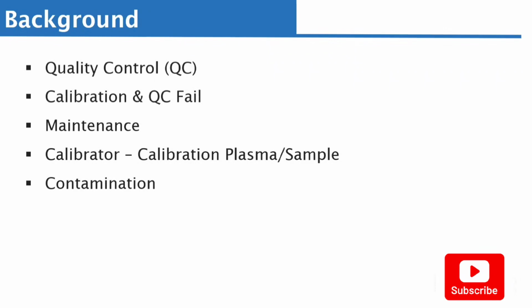Does that make sense? Now, in some other cases, each of these samples can come with a barcode. For example, if the analyzer scans the barcode for quality control, the analyzer will know that what I am doing now is for quality control, not for normal patient sample testing. In other words, sometimes when you scan the barcode, it can also know that this is for calibration plasma or for a calibration sample, so what I'm doing right now is calibration. The same way you do your patient sample is the same way you do the control, is the same way you do the calibration. The only difference is letting the analyzer know what you are doing.